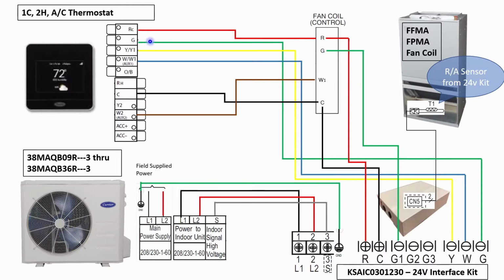Our G is going to run from our 24-volt thermostat to G on the interface kit, so that if the homeowner wants to turn the fan on for circulation, when they do that, the interface kit will still have control of the fan. And that way, when the unit's in defrost, it'll turn the fan off so as not to blow cold air on the occupants. The other G wire goes directly from the 24-volt interface kit G1 up to the fan coil.